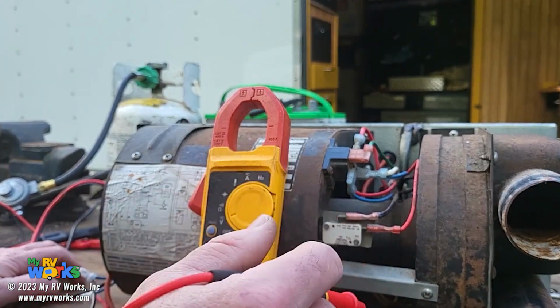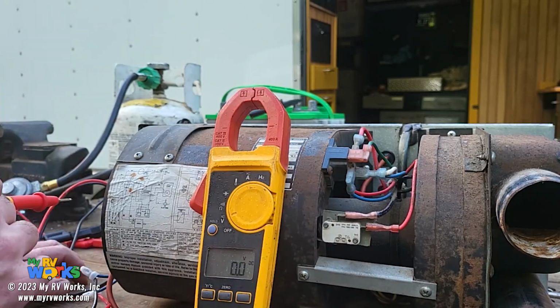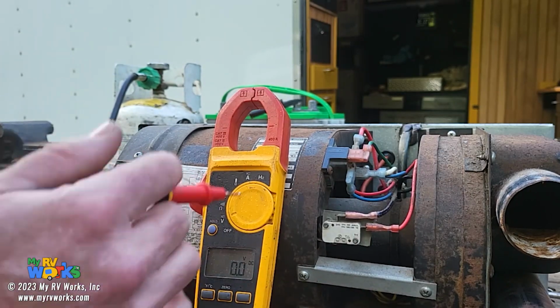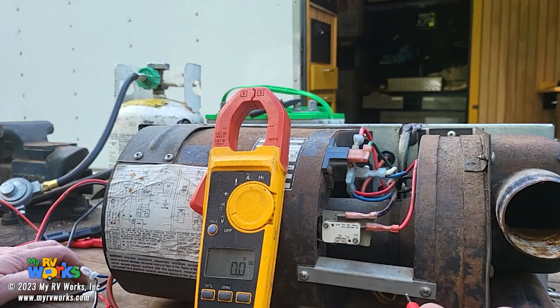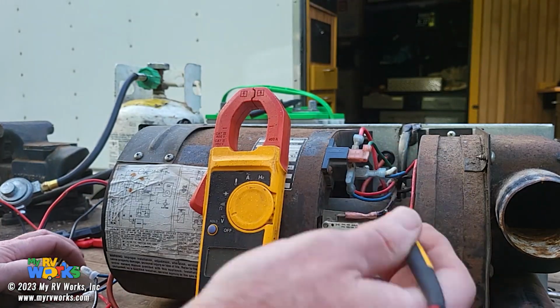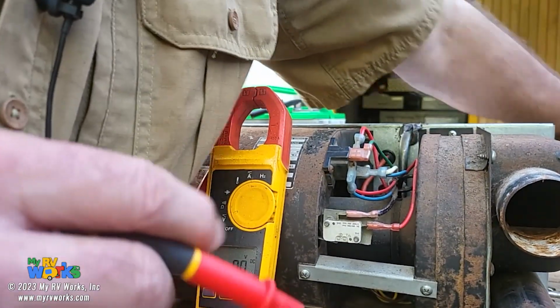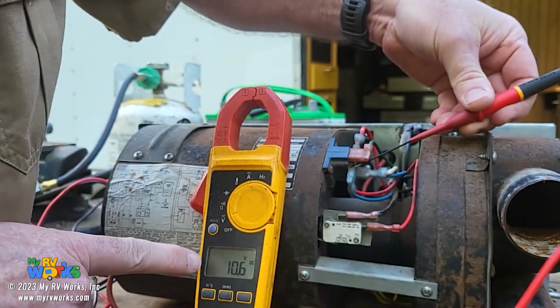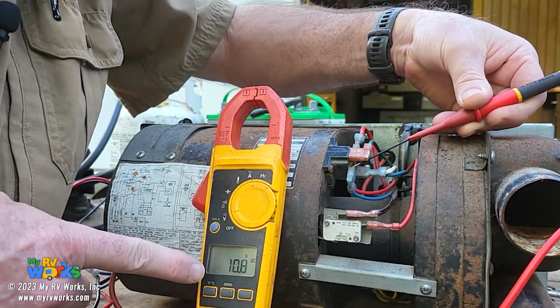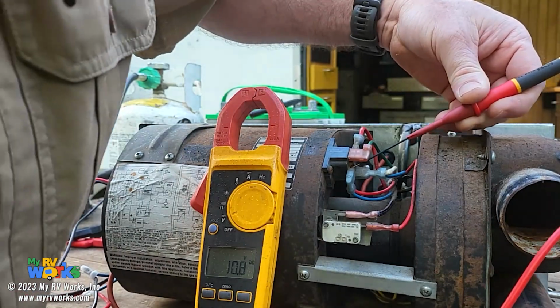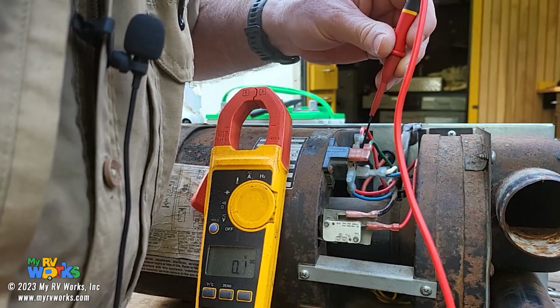We already know that the furnace is in a lockout condition because it's tried 3 times and it stopped. So why is the furnace just blowing forever? Anybody want to guess why? It has to do, let me get a pointy probe here. Anybody want to guess why? Well, we still have voltage coming in on our relay here, don't we? Yep, I've got 10 volts, which is basically 11. The question is, do we have a call for heat voltage, which is right here?